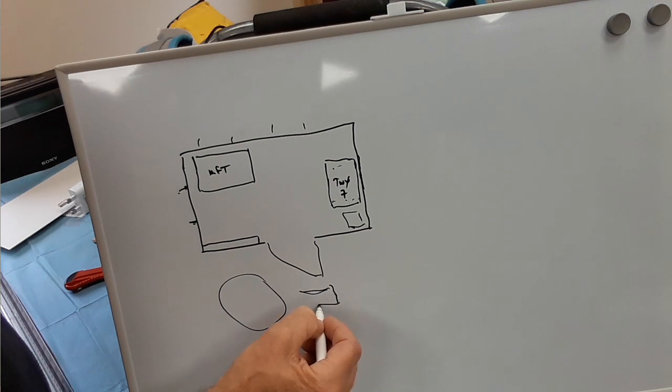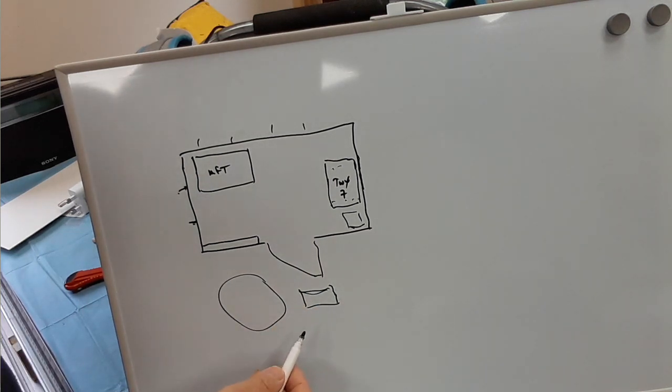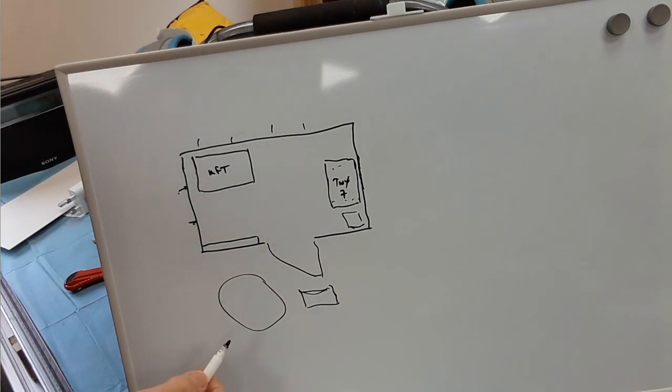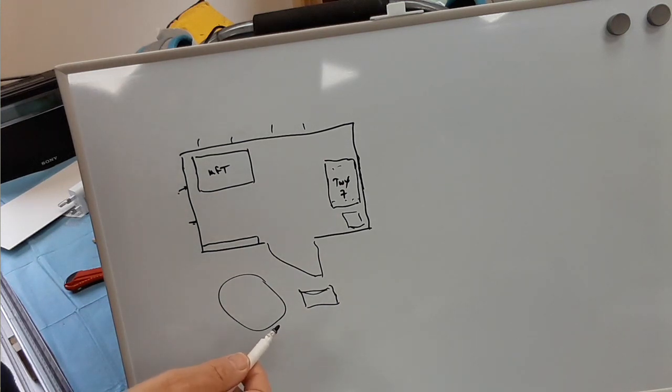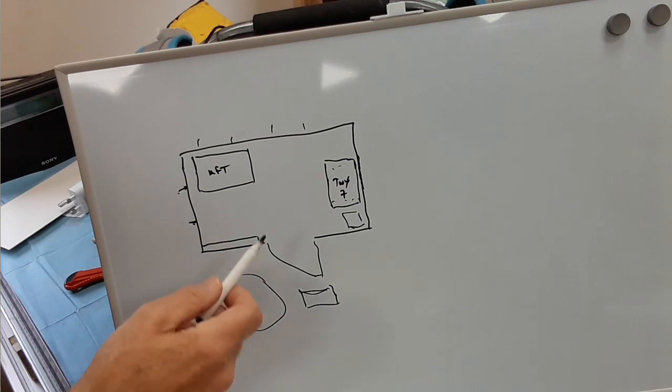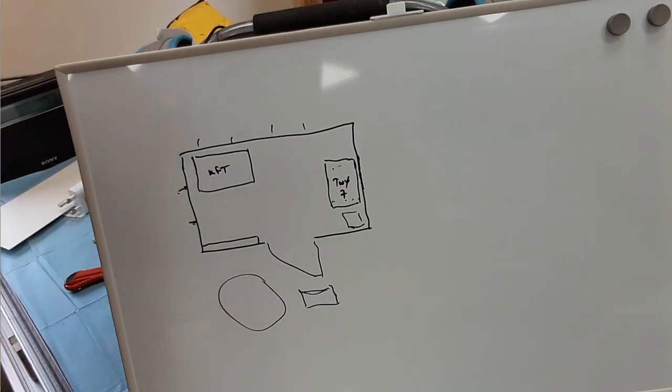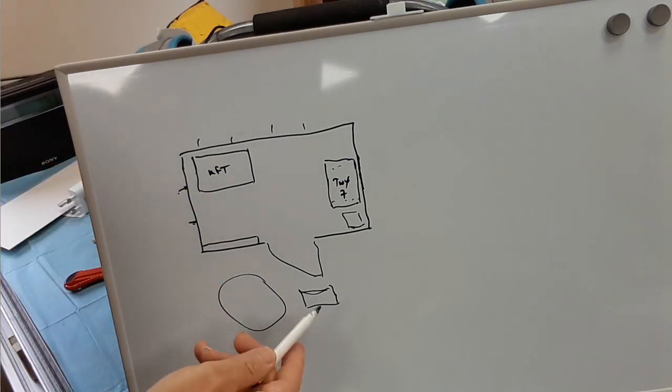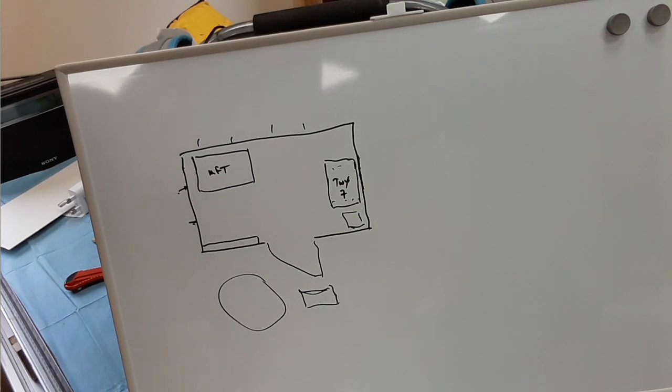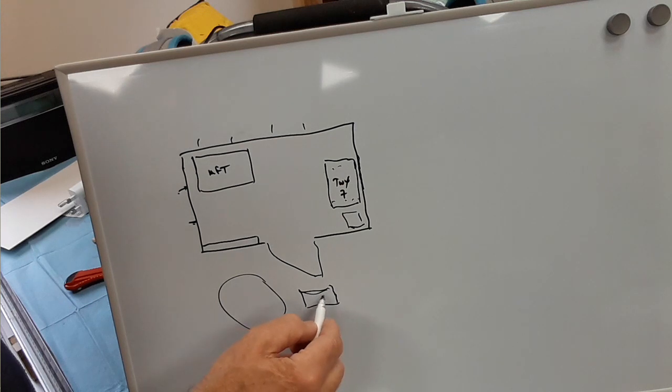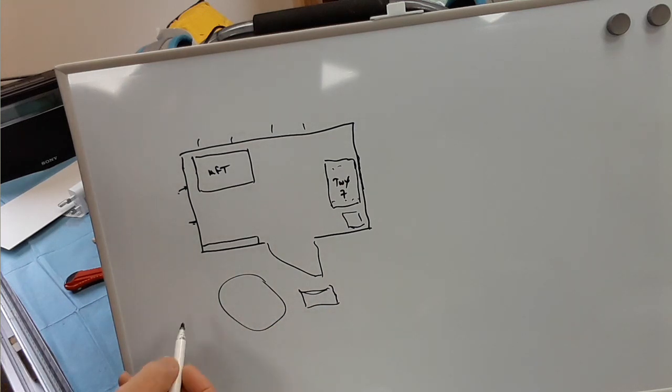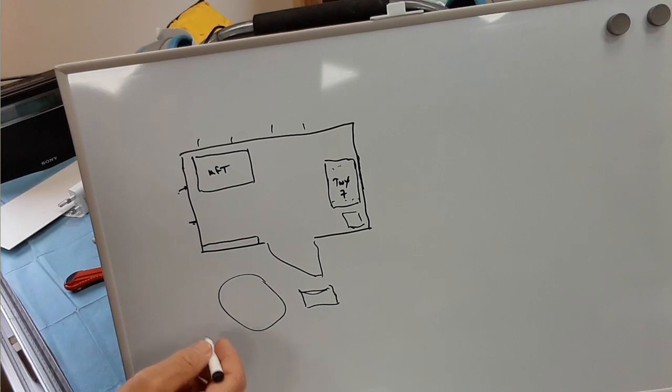4x2-ish which is square, clips nicely against the wall, very smart. And at some point I can't quite remember when, I'd emailed him and said I'm going to pinch that idea and he said yeah fine, more than welcome to do that, but be aware of the fact that the area of air moved through that pipe is nothing like the same as a four inch pipe, let alone a six inch pipe.